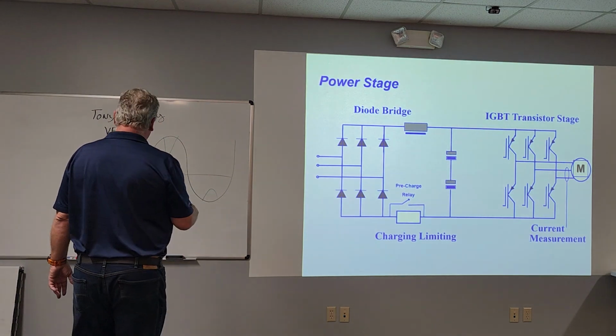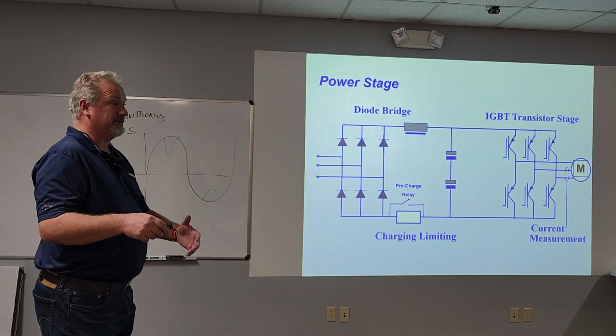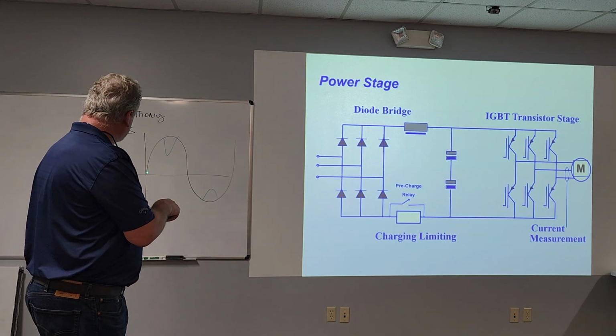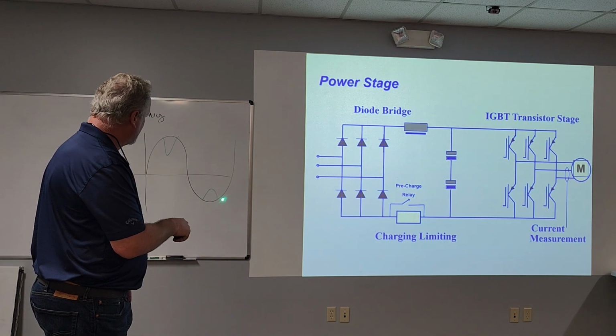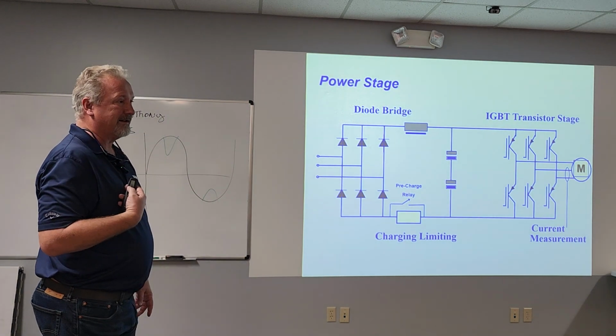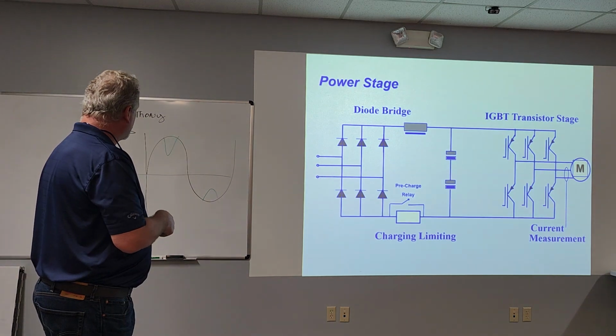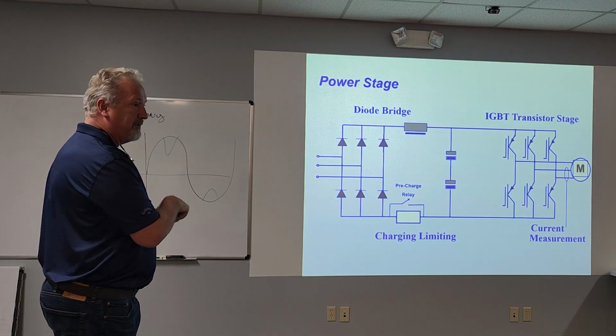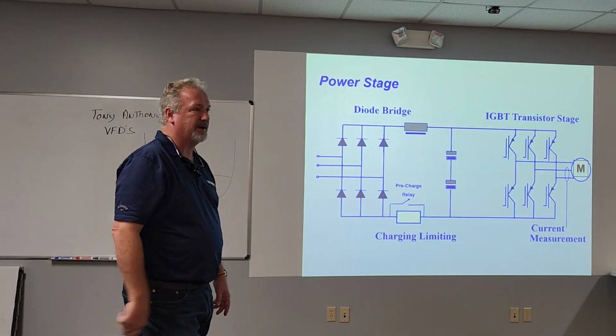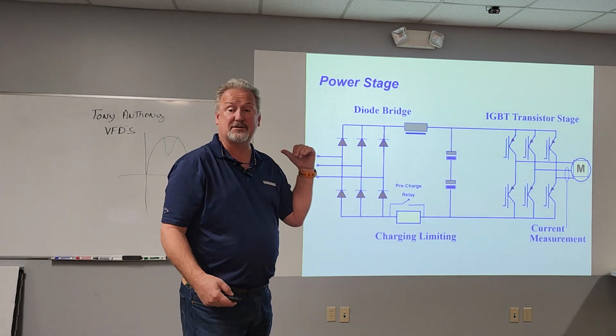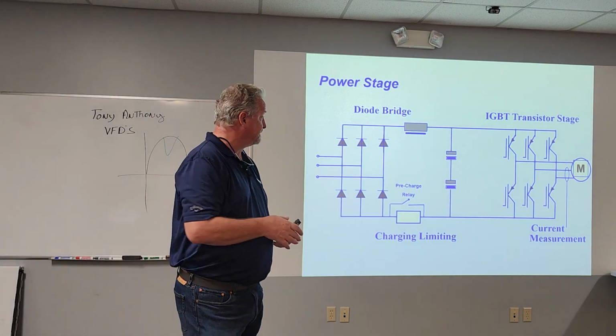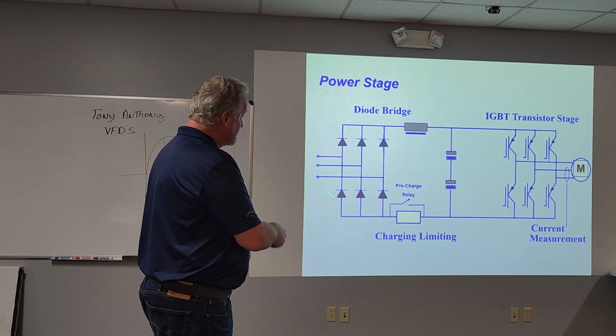A motor across the line starter is called a linear load. A linear load means it uses power across the whole sine wave. We're a nonlinear load. We only take power right here. It's sometimes called the camelback hump. It basically humps the sine wave. That's what's causing the harmonic distortion we're talking about.